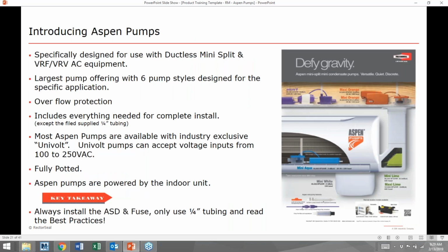Now, taking a look at the products, the product specifications that really set Aspen apart is that Aspen has products specifically designed for use with ductless mini split and VRF equipment. Some of our competitors have products that were used for some other application, and they just simply adapted them the best they could to work with this type of equipment. Because Aspen makes pumps specifically for ductless mini split applications, they also offer the largest offering with 6 different styles of pumps. We'll go through each of them in a little bit, but we have pumps that mount to the wall underneath the unit. We have pumps that go inside the unit. We have pumps that go in a drop ceiling above the unit or a remote location, and pumps that go off to the side of the unit in some trunking.